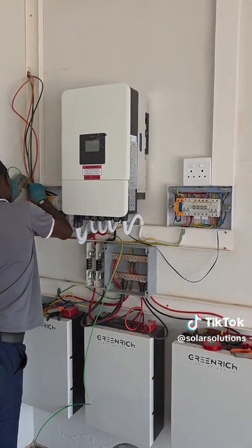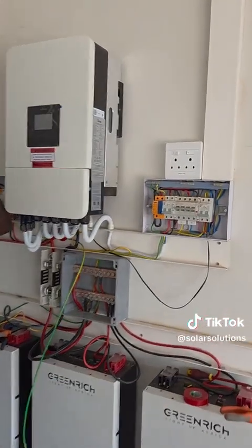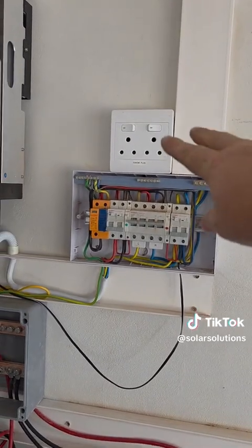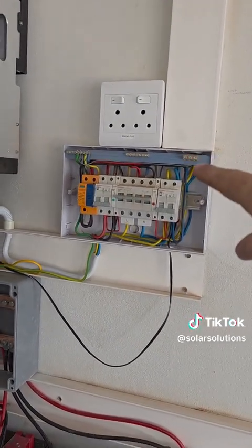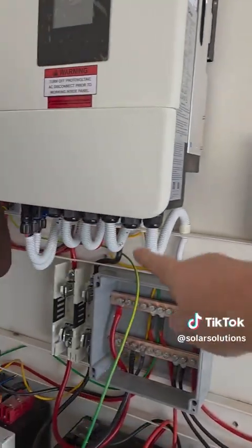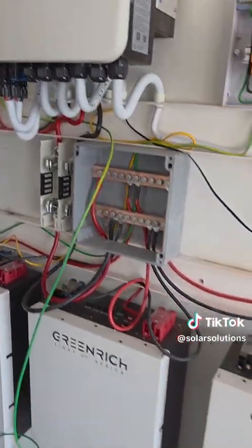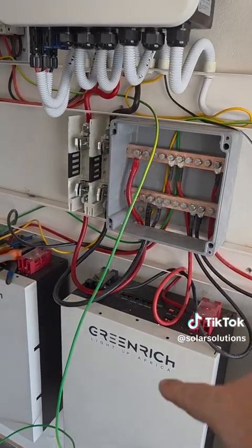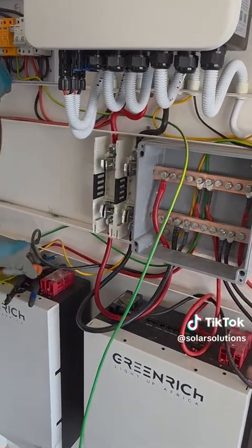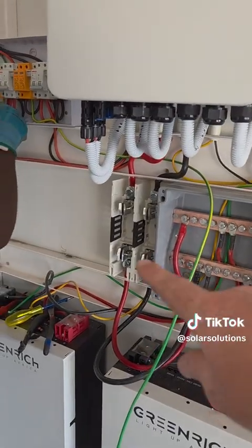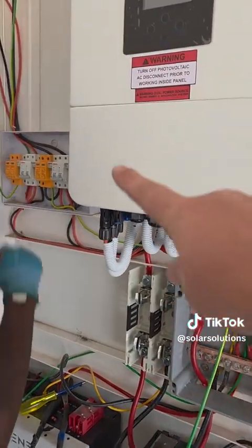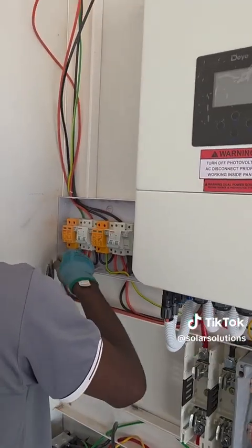Just want to do a quick last video before we close up. So we've got our AC combiner wired, we've got our AC cable coming down, we've got our ESCOM plug for the prepaid meter as well already wired, and then from the switchgear we're going to the inverter with the AC cable. We've got all our battery cables coming down, the earthing for the battery coming down, the communication cable coming down as well, and then of course from the bus bar we're going into the battery disconnect, and from the battery disconnect into the inverter, and Ford's just busy with the last wiring.